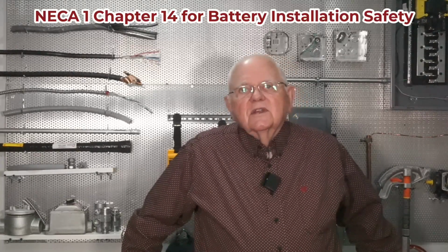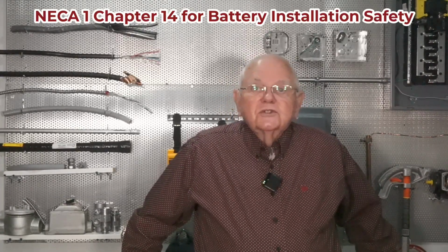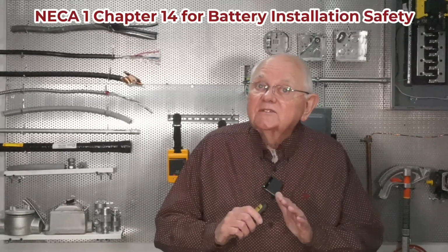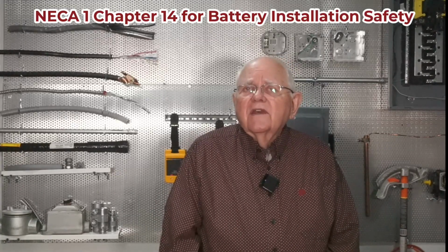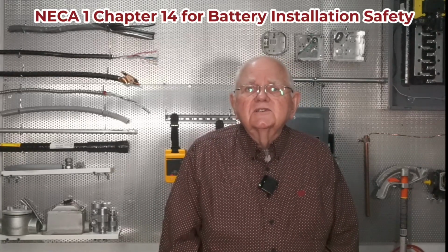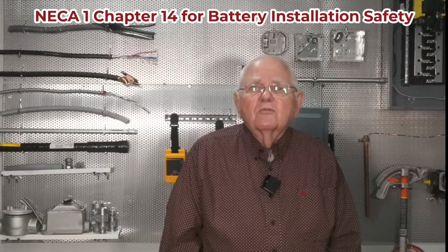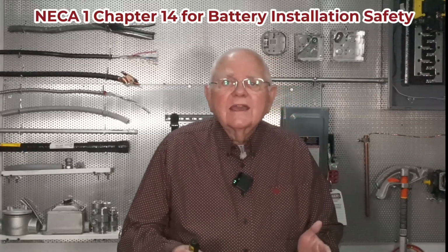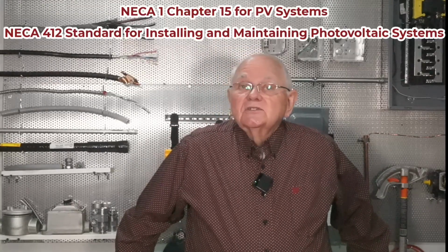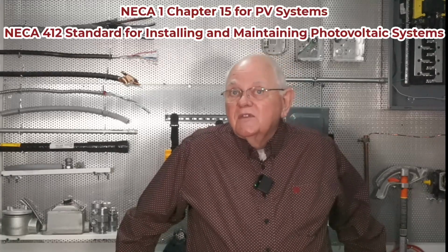But we have to consider the electrical hazard, certainly. My tools are going to be insulated. I also have to consider hydrogen. Something like a lead acid cell produces hydrogen gas, doesn't it? And that can be extremely flammable in certain concentrations. So ventilation in my battery room becomes important. How to install my rack. When I put my cells in the rack, I always start from the center and work out, the NEIS tells me. Chapter 15 of the NEIS 1 addresses the installation of solar photovoltaic systems, PV systems.